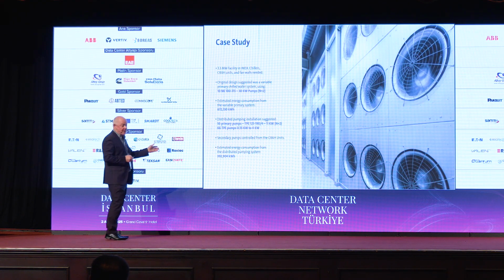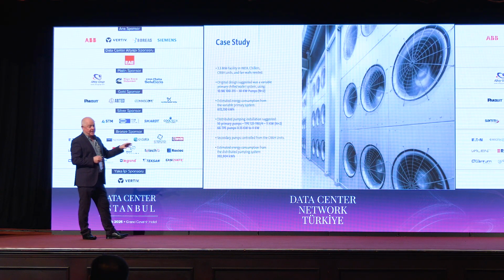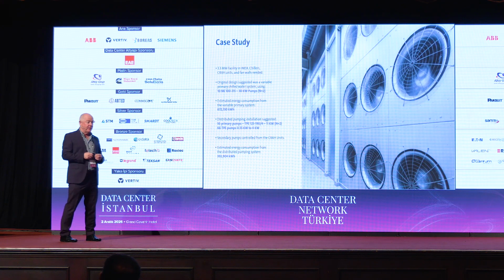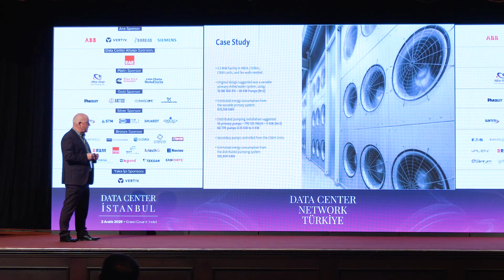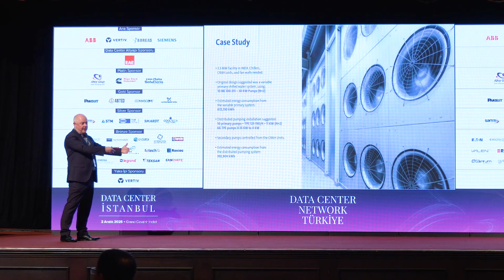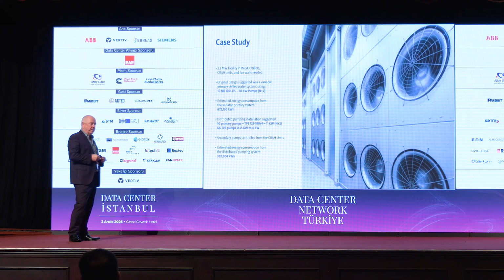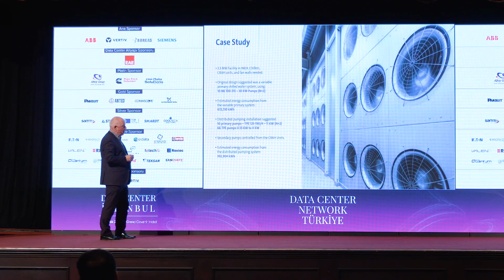And what we're not measuring and what we're not showing here is the efficiency on the chilled water system. And as I mentioned, we've measured this in some places and we're getting up to 14, 15% on the overall chilled water system because it's fully balanced. So there's huge energy savings to be made. It's modular, which makes it easy to build a system. If it's a colo or whatever and you're getting clients in over time, we can make it work very efficiently from day one right up to when the full load is on the system. Or if it's a system where we plan for expansion in the future, once again it lends itself to that modularity.